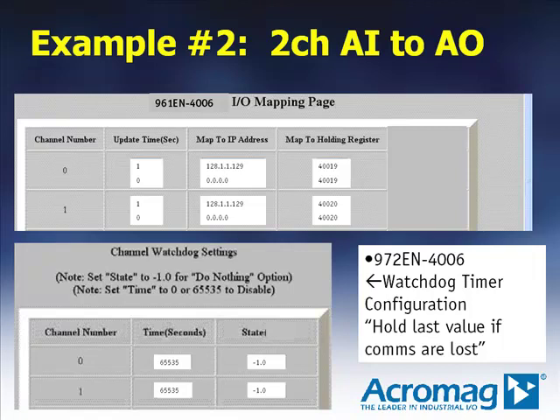The top screen capture shows how to configure channels 0 and 1 on the analog input module. Both channels are set for one-second updates and will be mapped to the same IP address. Two different Modbus registers are shown, which indicate two different output channels on the analog output module. The bottom screen capture shows how to configure the watchdog timer and output state values for the analog output module. The watchdog timer is set to 65535 and the output state is set to minus one, which means they are disabled. So in the event of communications loss to the output module, the analog output channels will hold their last values indefinitely until updated properly by the input module.